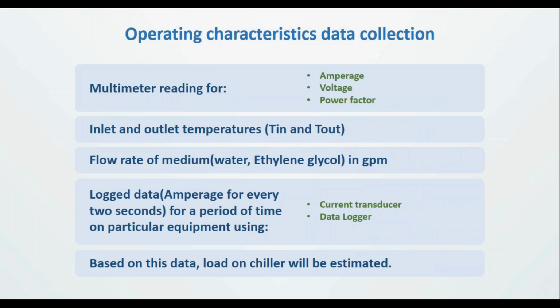So we do measure, and the measurements, as I said, are more like a snapshot. We may, in some cases, leave the electrical measurement loggers and transducers on for a few days, but there is no substitute for continuous measurement. That is what would be ideal. But anyway, we would measure the current, the voltage, the power factor. We would also measure the flow rate of the medium. We would definitely do that, as well as the temperature differences. So that tells us a lot about the load profile, the part load profile of the chiller.